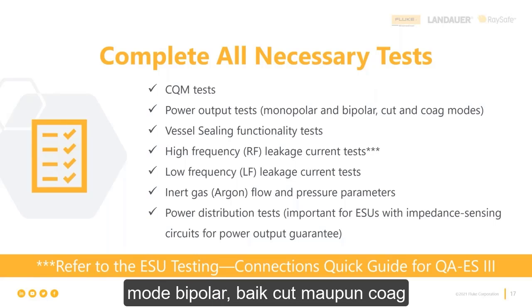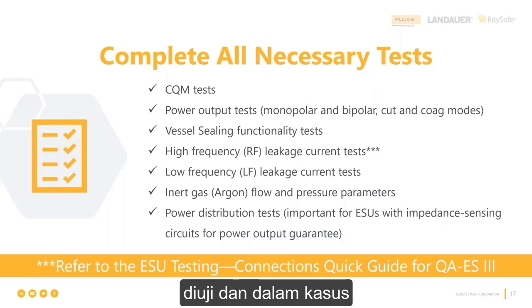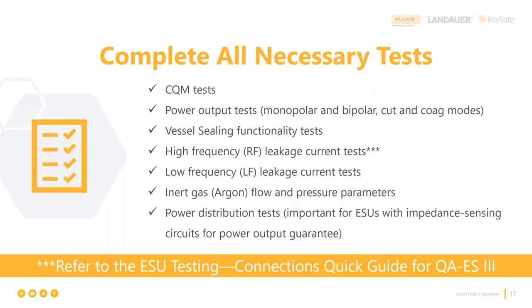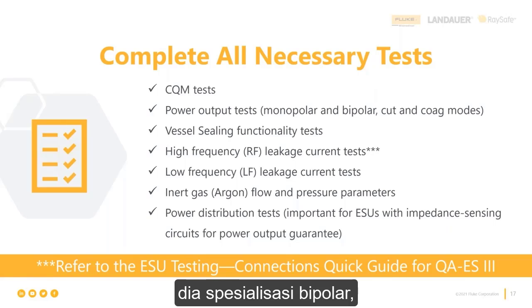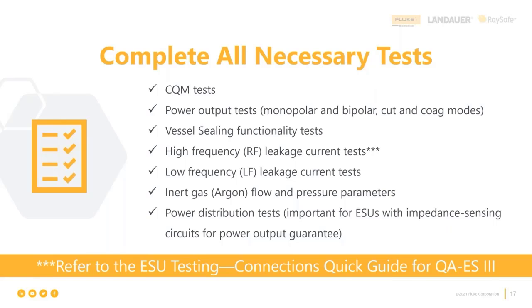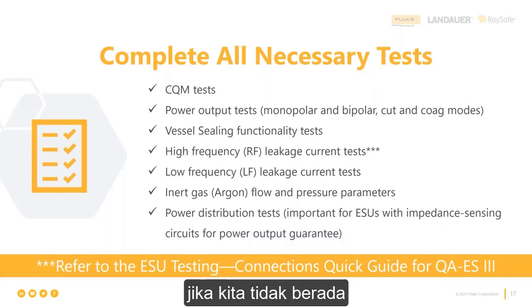And then there's the power output tests for both monopolar and bipolar modes, both cut and coag. So those tests need to be done. Vessel sealing, if the ESU has vessel sealing functionality, that needs to be tested. And in the case of Valleylab, their vessel sealing mode, even though it's a specialization of bipolar, cannot be properly tested without being in the service mode.